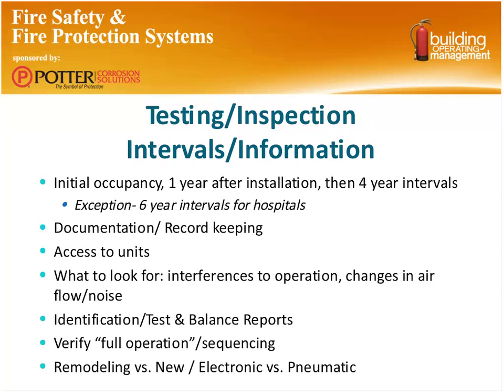I'm going to bring up one point as we still are on this testing and inspection slide, and that's relative to the life safety of stairwell systems. A lot of stairwell systems have a positive pressurization system in them, and that's to allow occupants to evacuate and not have smoke entering into that stairwell. When that happens, what we found in a lot of cases is the pressure sensors get out of calibration, and if you overpressurize a stairwell, what can actually happen is, to a person trying to egress through that stairwell door, the pressure can actually make them feel like it's locked. And it's been proven that most people will not push too hard on the door because they're assuming that it is a locked condition.